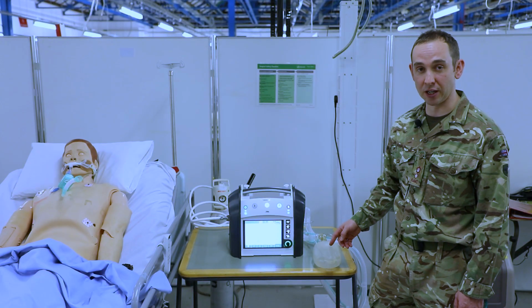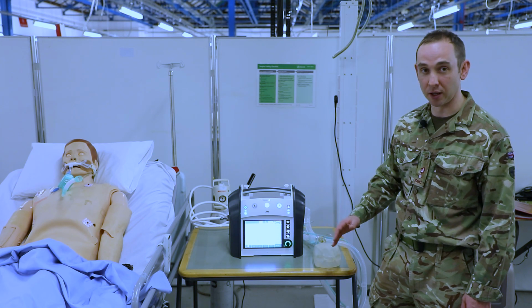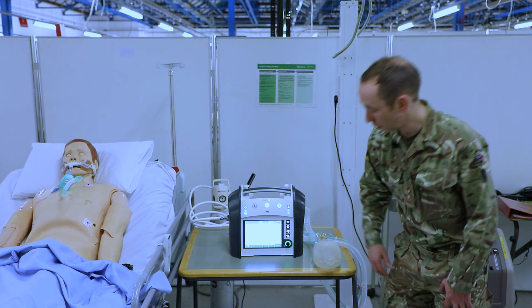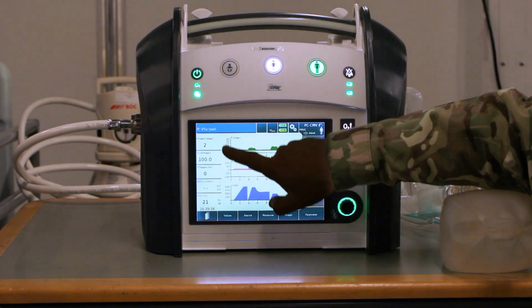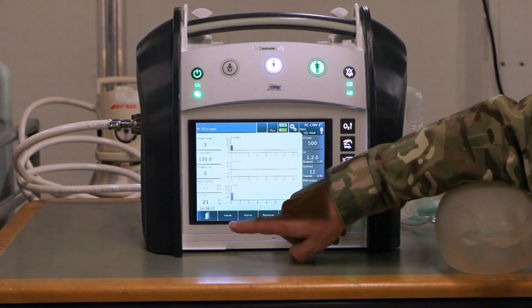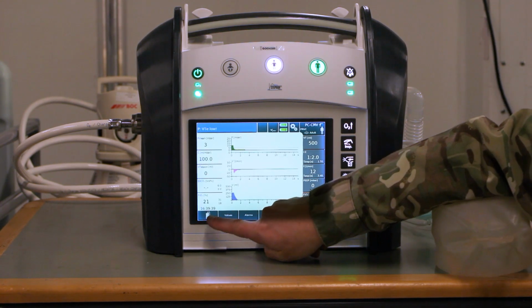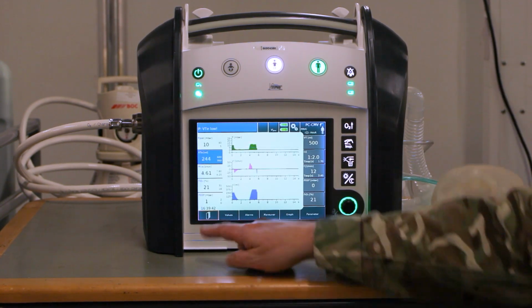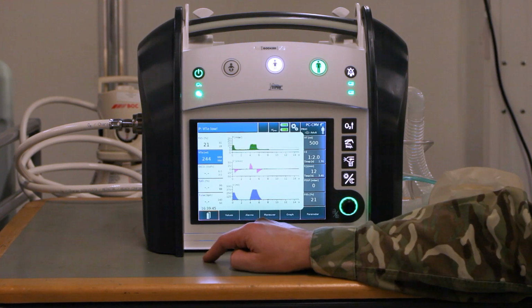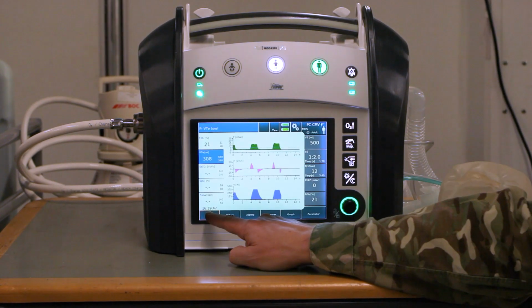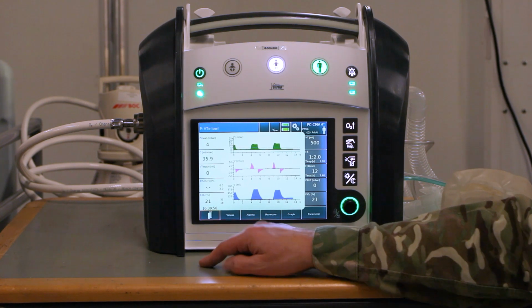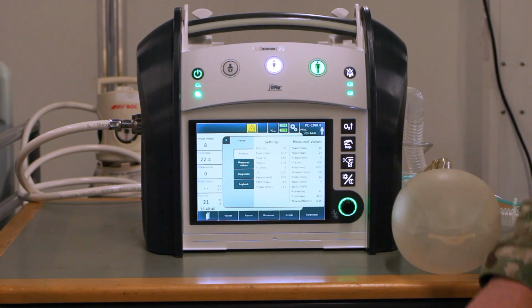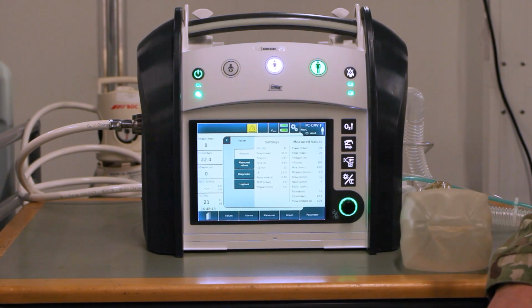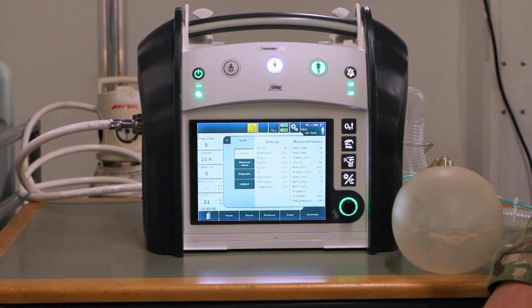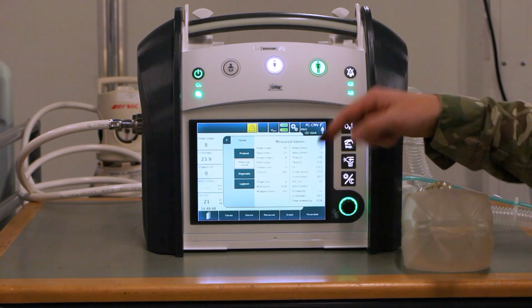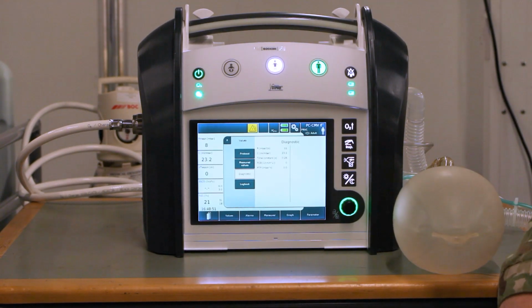Having a test lung attached at this stage is really advantageous to ensure that the ventilator can ramp up to the appropriate level. When we now look on the left hand side, this will give our values that have been measured. If you press the button directly underneath, this will cycle through various different values, and these can be pre-programmed via the settings button for the individual user as required. The next button along is the values button. This will give you a comprehensive set of measurements of patient values that, if you click through, will give you plenty of information, including compliance and resistance.